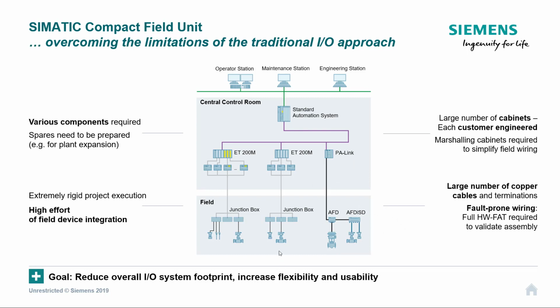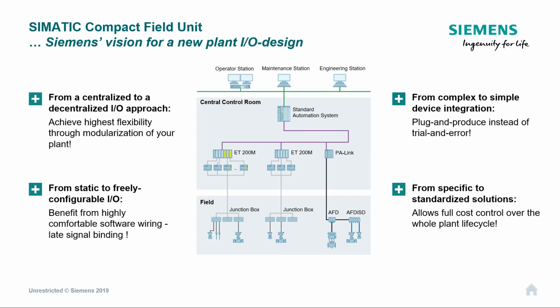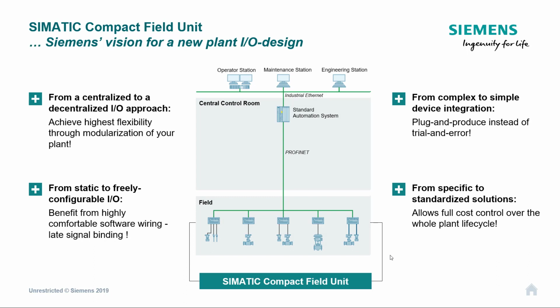What we're trying to do is bring Profinet into the field, and that's what the Compact Field Unit does. So it supports media ring redundancy. Not really showing it on here, it is just a sketch, but we take our Ethernet cable out, which has got Profibus on it, so Profibus over Ethernet is called Profinet.